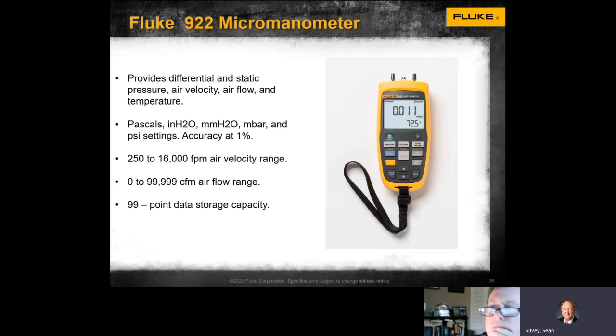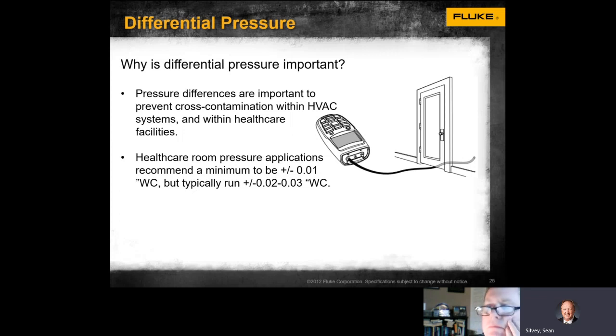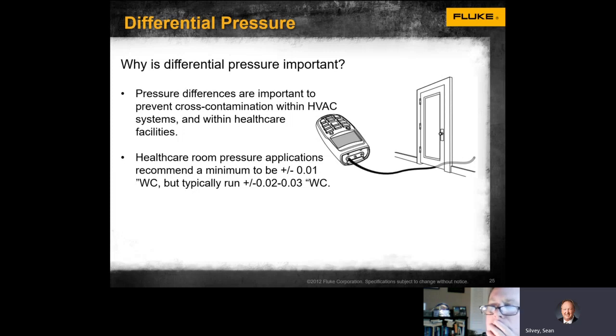The next item is the Fluke 922 manometer. This is crucial because it allows you to perform differential and static pressure tests, air velocity, airflow, and temperature measurements. The differential pressure capability is especially important in systems where you need positive pressure on one part of a room and negative pressure on another — critical in healthcare, operating rooms, labs, and pharmaceuticals where you want to keep positive pressure inside so that when a door opens, nothing comes back into that environment.